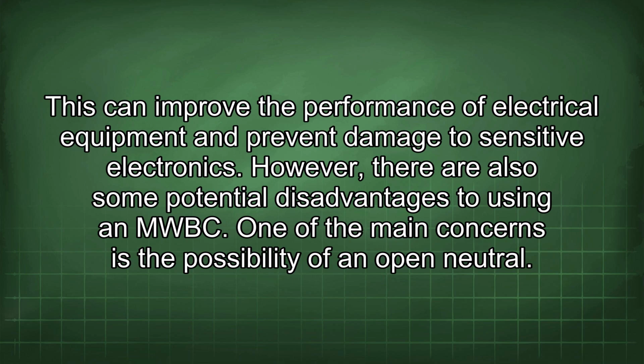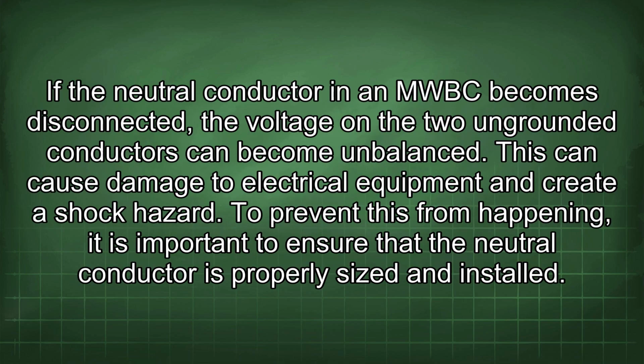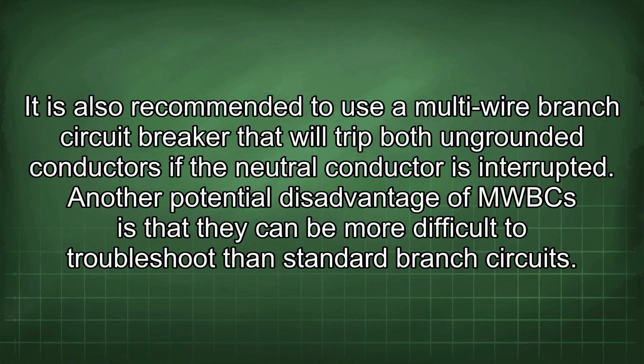However, there are also some potential disadvantages to using an MWBC. One of the main concerns is the possibility of an open neutral. If the neutral conductor in an MWBC becomes disconnected, the voltage on the two ungrounded conductors can become unbalanced. This can cause damage to electrical equipment and create a shock hazard. To prevent this from happening, it is important to ensure that the neutral conductor is properly sized and installed. It is also recommended to use a multi-wire branch circuit breaker that will trip both ungrounded conductors if the neutral conductor is interrupted.